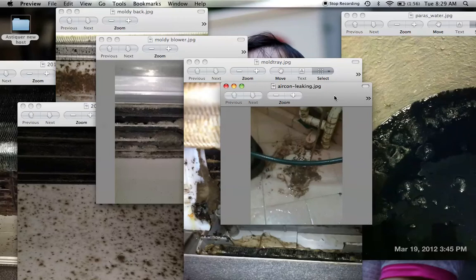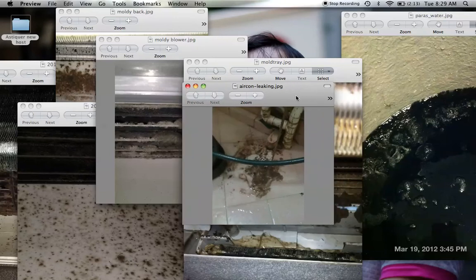We're gonna cover the most common type of aircon water dripping problem, which is clogging of the drain tray or the drain pipe by a jelly-like substance. This jelly is what we flush out from the aircon condensate pipe that is buried in the concrete and out into the toilet. This is a picture taken in one of the HDB estates, where the condensate water pipe is on the external part of the toilet, and after flushing you can see this jelly.